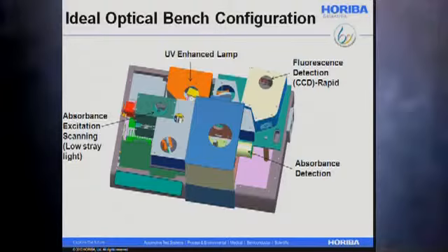And the real breakthrough in speed comes from being a system that incorporates a CCD to collect data up to 100 times faster. So previous scanning instruments were actually limited in terms of the utility for monitoring the disinfection byproducts on a continuous online monitoring system because the scans took 25 to 90 minutes.